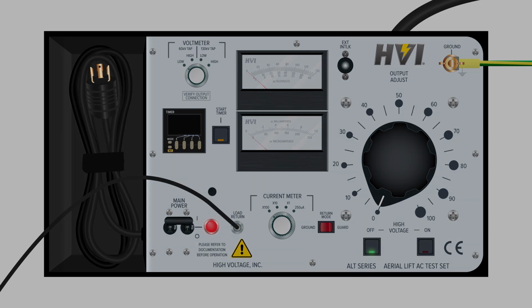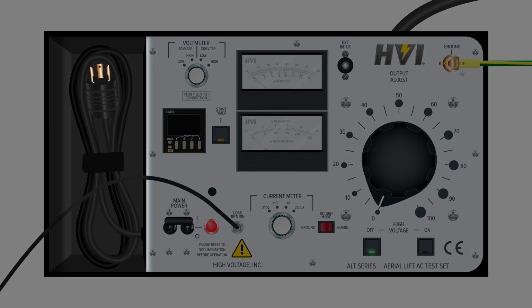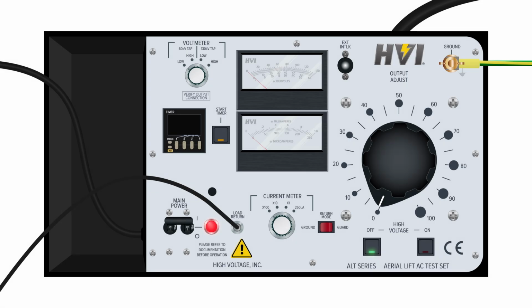Finally, use the supplied power cord for the main control unit to connect to a grounded power source. You've now properly connected the high voltage section to the main control panel, grounded the two sections of the ALT130, connected the high voltage connection lead to the high side of the DUT, and connected the return lead from the low side of the DUT to the control panel.